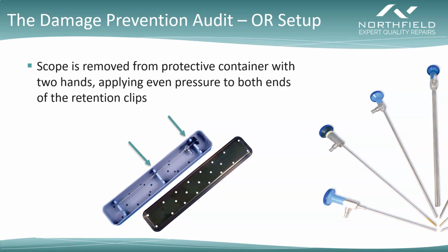Well, inside that scope are rod lenses that are made of glass, and there are anchor points that are holding those rod lenses in place. And that pressure causes the scope to flex just a little bit, which can cause those anchors to break or that glass to break, and it can do a lot of damage over time. So we want to make sure that the scopes are being picked up with two hands, applying even pressure where those retention clips are in place.